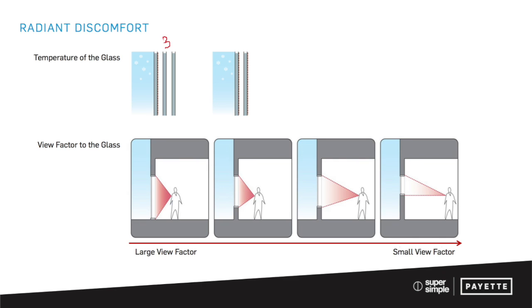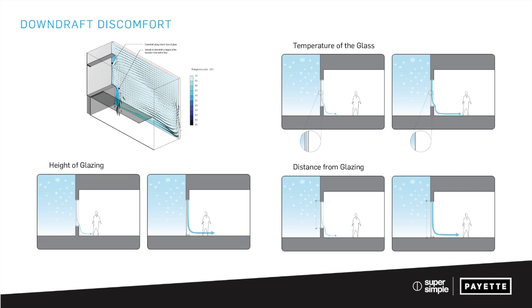The other factor is what we call the View Factor (V factor) — how much of your body's field of view is that glass occupying. If it's a really big window and you're standing really close to it, like your studio desk is right next to a floor-to-ceiling piece of glass, you're going to have a very big V factor. If you're in an old building with punched windows and you're three desks in, you're going to have a very small V factor because the glass is a very small percentage of what you're seeing. So the smaller the window and the further away you are will impact whether or not it makes you uncomfortable.